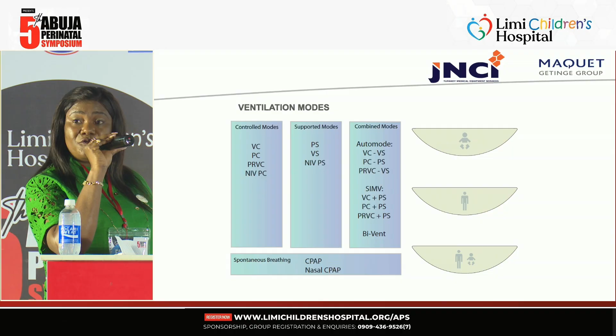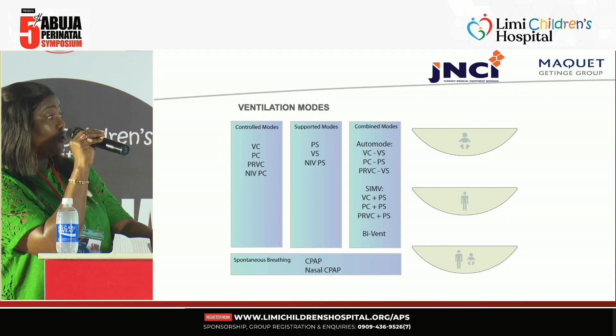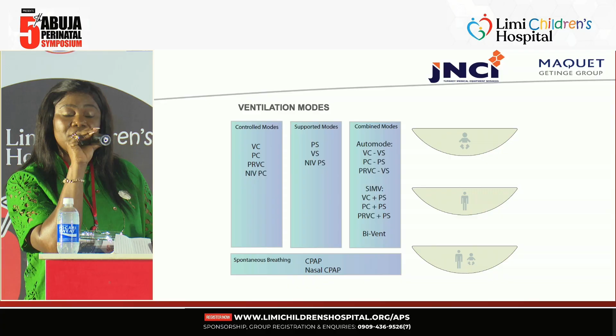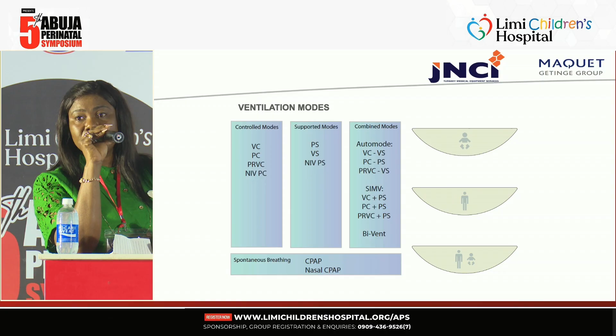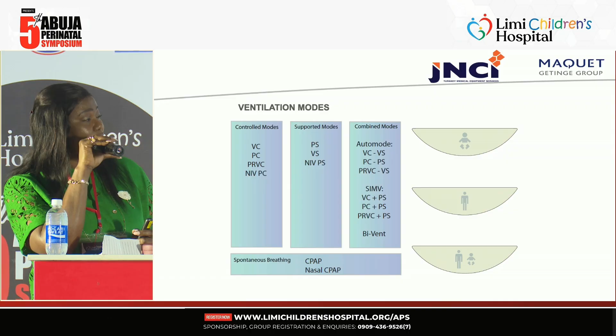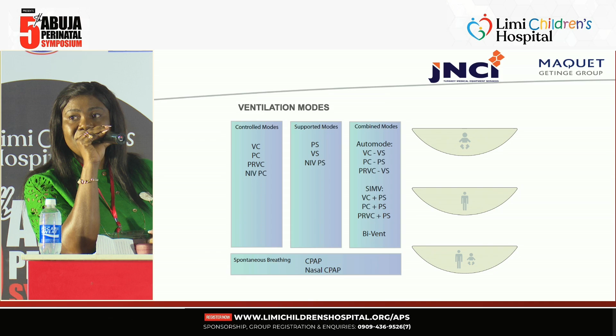It is capable of doing ventilation modes, both advanced and basic ventilation modes, like the control modes where you have your volume control, your pressure control, your pressure-regulated volume control, and your non-invasive pressure controls. And we have support modes. All these modes, some of which come as a standard, and other modes are requested for, and they can be put on the ventilator for you. And then we have our combined modes where we have volume control with support, pressure control with pressure support, and pressure-regulated volume control with support. And our autonomous modes of integration, that's interactive modes where we have your SIMV, synchronized intermittent mandatory ventilation. And in non-invasive modes, you can use it for your CPAP. So it can be used as a CPAP device as well in non-invasive mode.